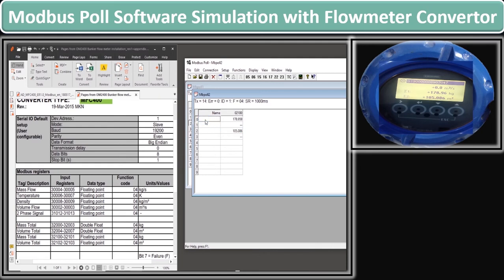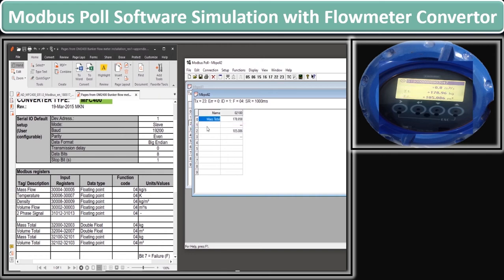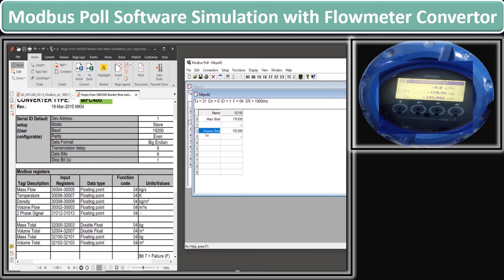We set the formatting again by selecting 32-bit Float data type and Big-Endian data formatting on both registers 0 and 2 respectively. You will see that we start getting the real values. We then give tag names to clarify the values: the first tag is Mass Total and the second tag is Volume Total. You can see the same totalizer values on the totalizer screen of the flow meter as well.